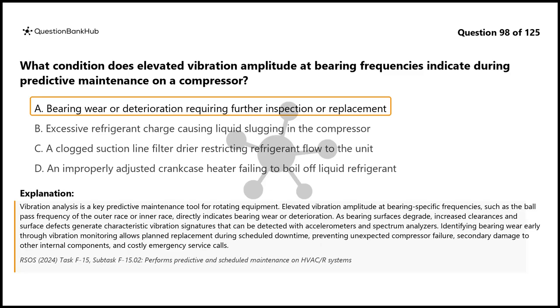As bearing surfaces degrade, increased clearances and surface defects generate characteristic vibration signatures that can be detected with accelerometers and spectrum analyzers. Identifying bearing wear early through vibration monitoring allows planned replacement during scheduled downtime, preventing unexpected compressor failure, secondary damage to other internal components, and costly emergency service calls.